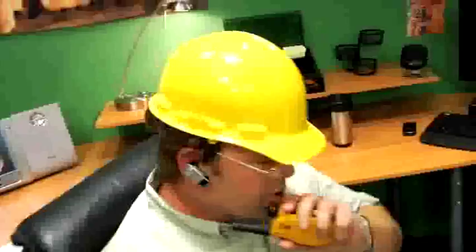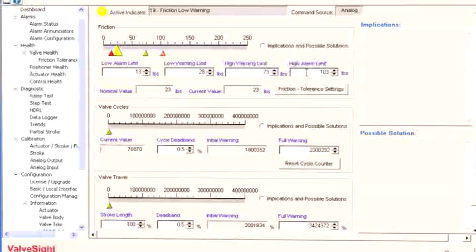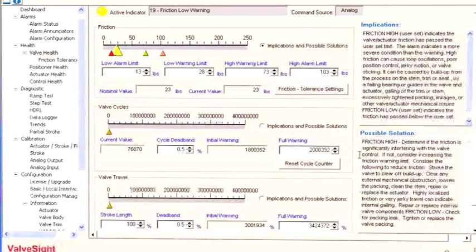ValveSight will also gather and store trend information in the four critical areas of the valve. You can ignore the DCS warning on FCV 1077, but I can get someone down there to tighten up the packing follower before it turns into a major problem. I'll let you know once we're done.